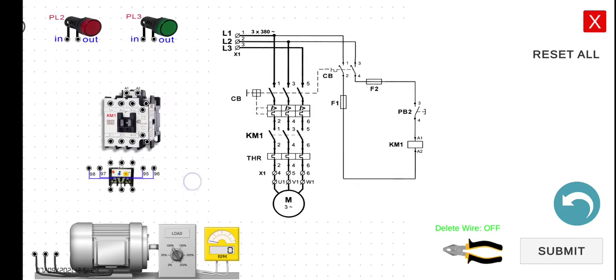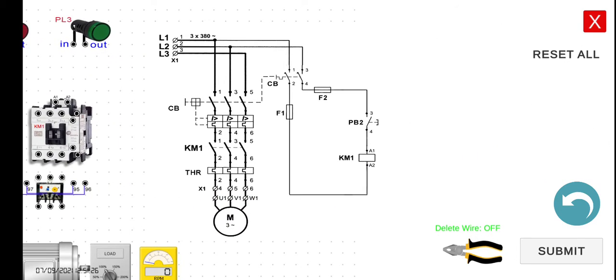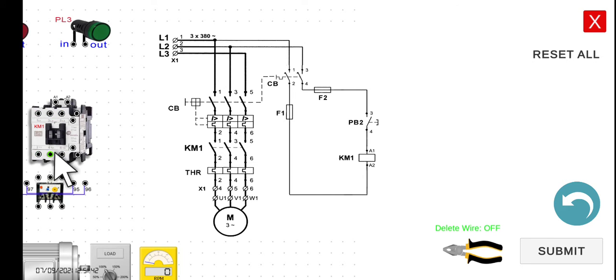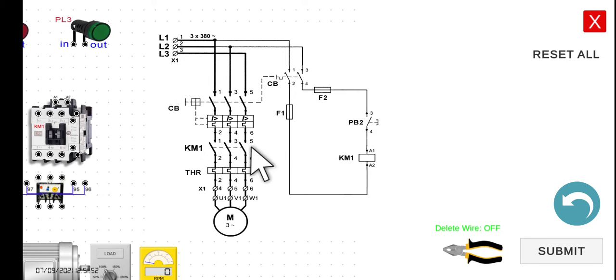So let's discuss the functionality of the circuit. This is a very simple circuit. As of the moment we turn on the breaker, the motor will not run because there is an open circuit here. We will be using the main contacts of our magnetic contactor around here. So as of this moment, when you start the circuit breaker, this one is open — these are normally open main contacts.